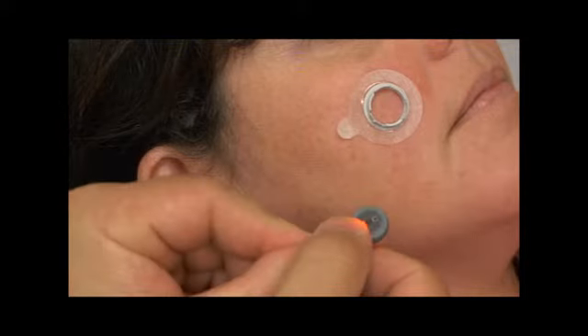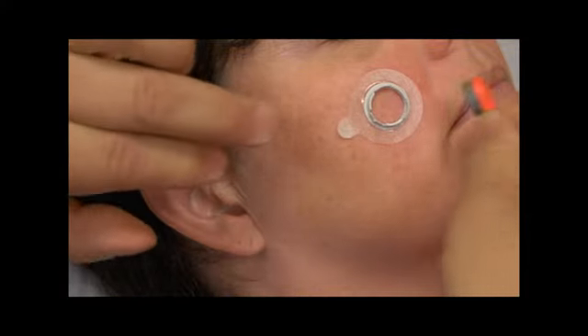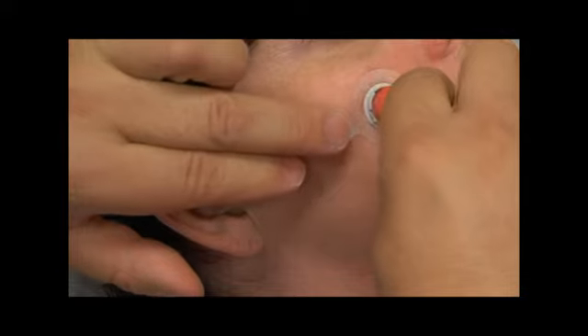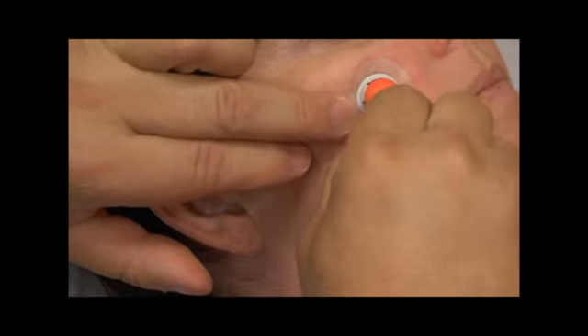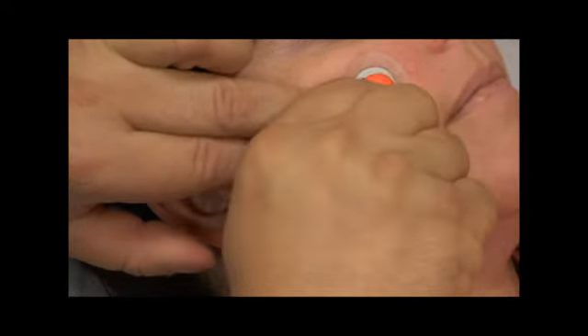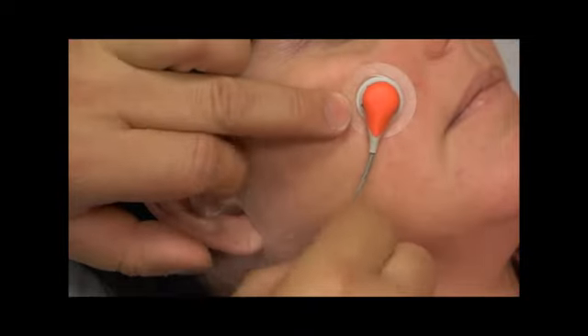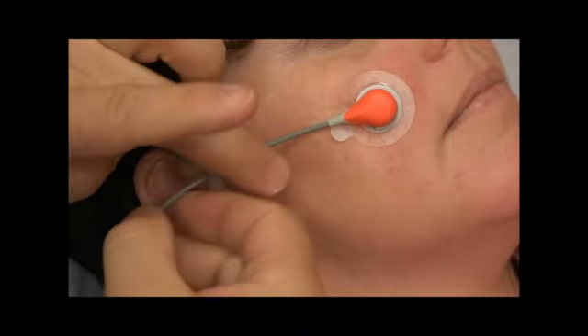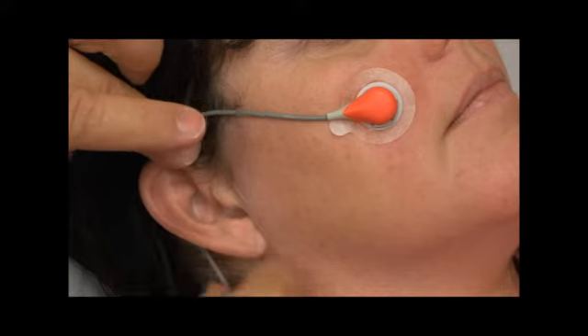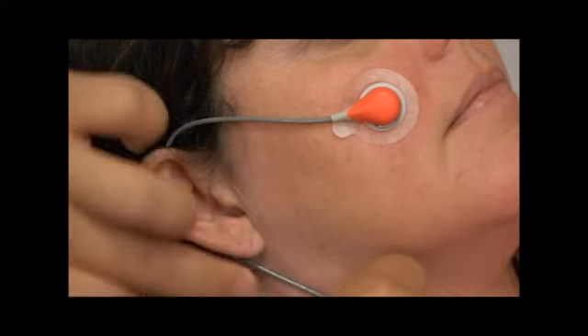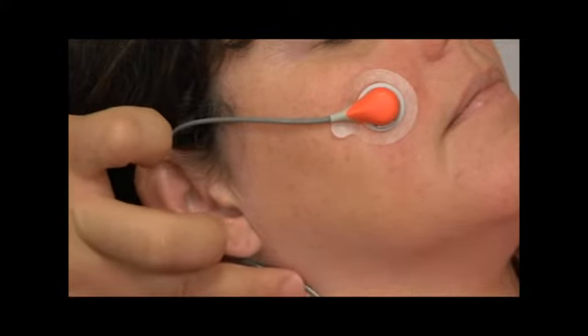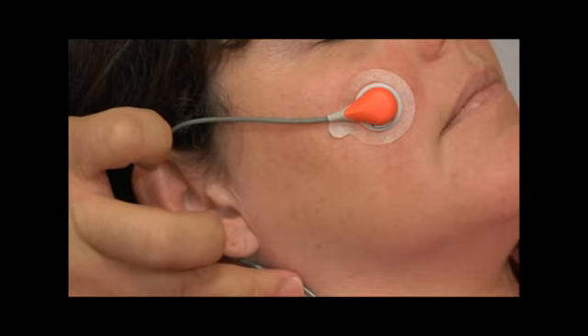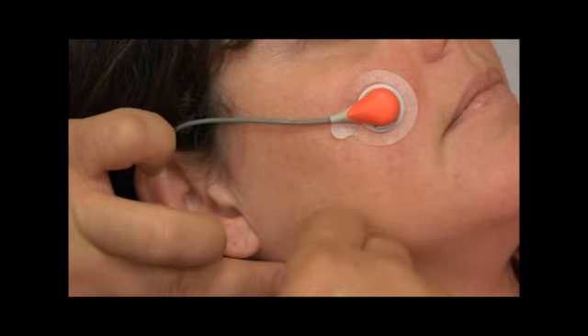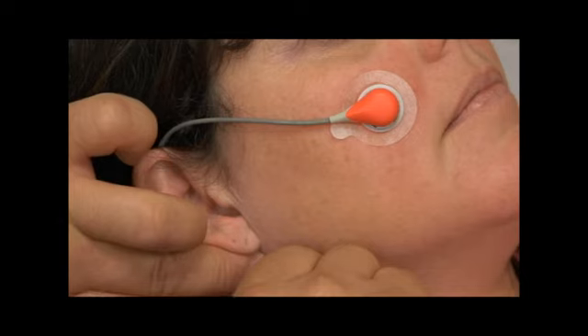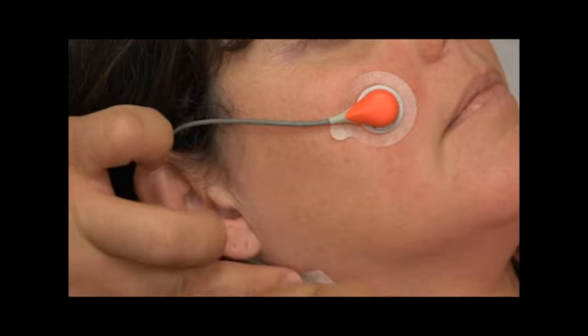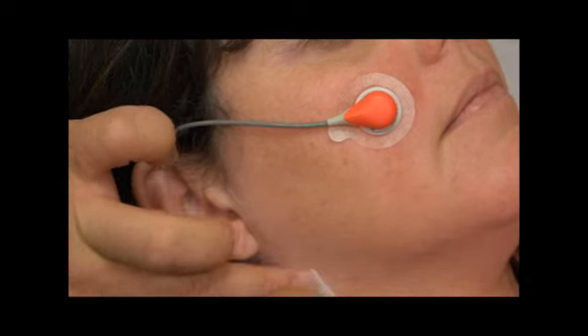Holding the sensor at the cable strain relief, approach the MAR from the flap side and first insert the nose of the sensor into the ring. Then apply a slight downward pressure on the cable strain relief. The spring tension of the application device will pull the sensor into place with little to no pressure on the skin. Slightly twist the sensor in the ring and press the sensor gently to ensure distribution of the contact liquid and contact with the skin. For forehead or cheek placement, wrap the sensor cable once around the ear and tape the cable to the cheek.